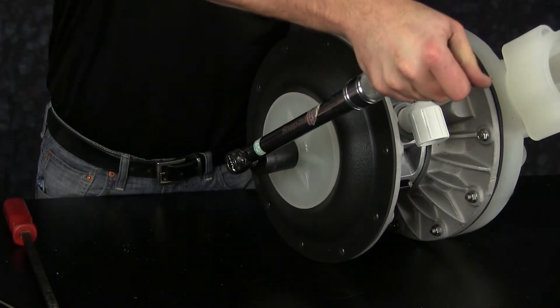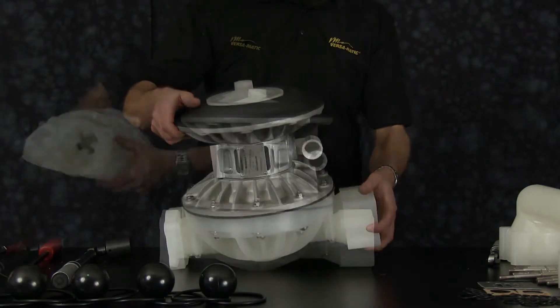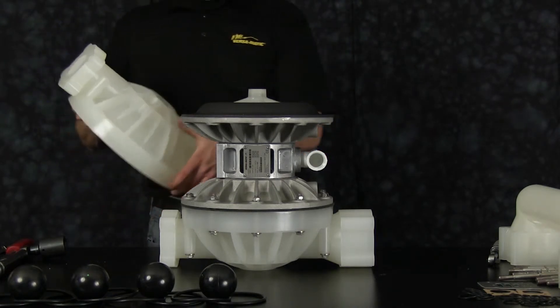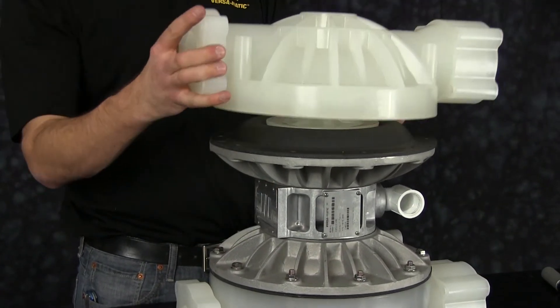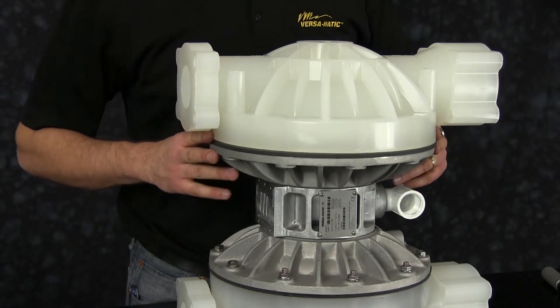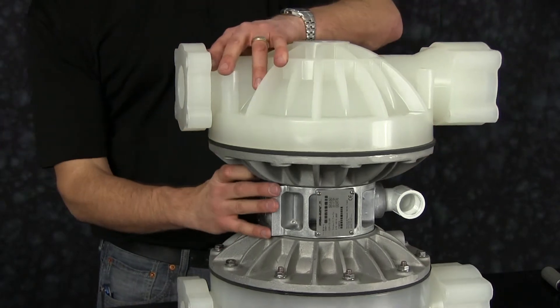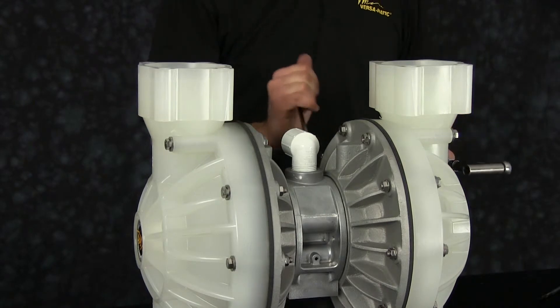Torque the diaphragm assembly to the specified torque. If you achieve torque between bolt holes, always go to the next hole. Inspect the machined surfaces of the outer chambers. Note the orientation of the outer chamber — the discharge side should face towards the main air valve assembly. Install our outer chamber bolts. When tightening down the outer chamber, be sure to tighten the bolts in a cross pattern and torque to specification.